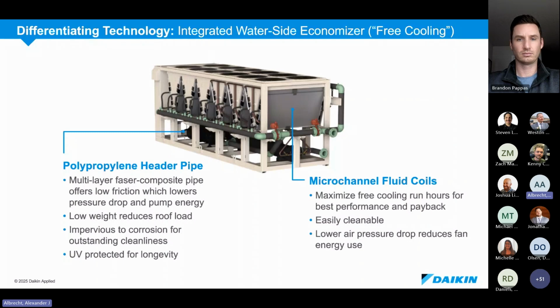And then, as mentioned, the Pathfinder AWV has an optional water side economizer, mainly for process cooling. We utilize a microchannel for the fluid, which is optimized for a single aluminum alloy, able to avoid risk of galvanic corrosion, which tube and fin coils are susceptible to, easily cleanable, as well as low air pressure drop. And then for the header, we utilize a polypropylene header pipe selected in order to lower friction, as well as eliminate corrosion, and also for low weight to reduce the roof load. So all of these are ideal choices for improvements and leader in efficiency on water side economizing for free cooling.